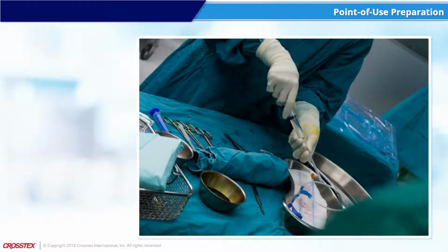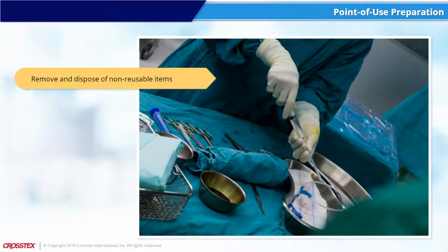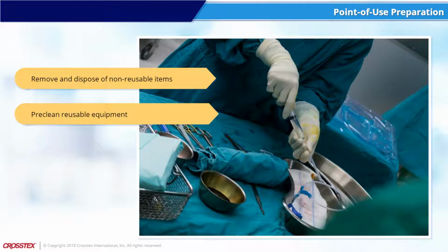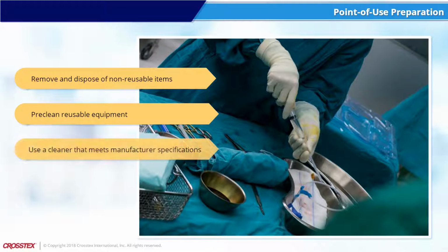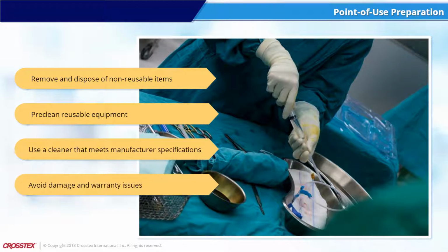Point of use preparation. This step begins with removing and properly disposing of all non-reusable items, such as tubing and packaging, etc. The point of use preparation involves pre-cleaning the reusable equipment or instruments with a cleaner that meets manufacturer specifications. It is important to use the right type of cleaner to avoid damage to the equipment and warranty issues.